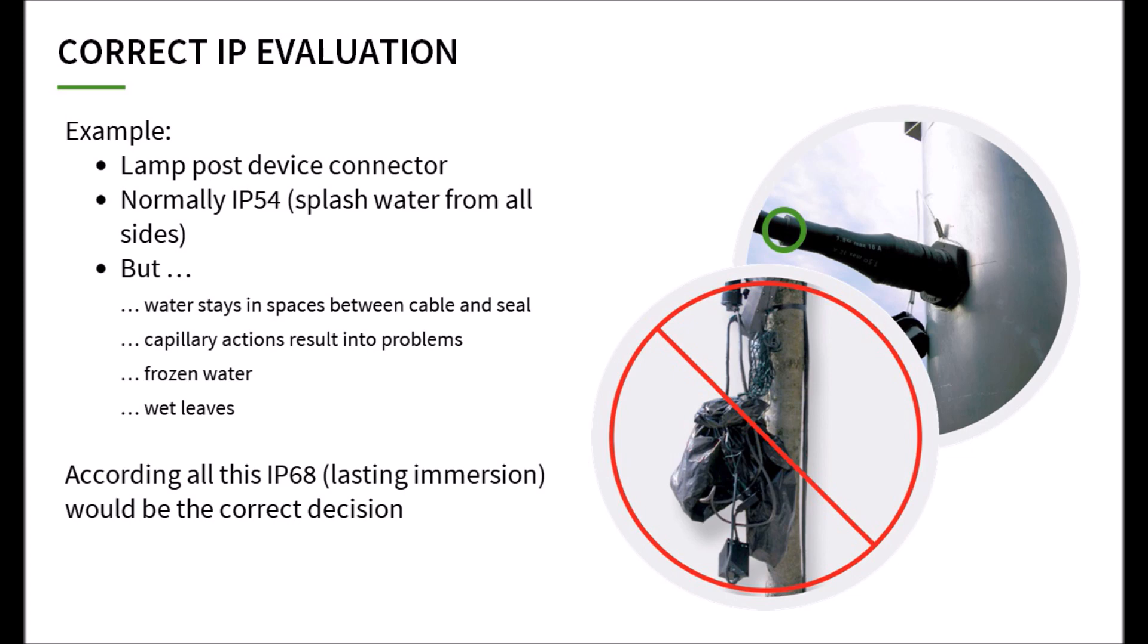This is due to a small reservoir that is located between the cable and the seal. After a rain shower, this space fills with water and remains there. Over time, the water penetrates into the interior of the housing via capillary action.